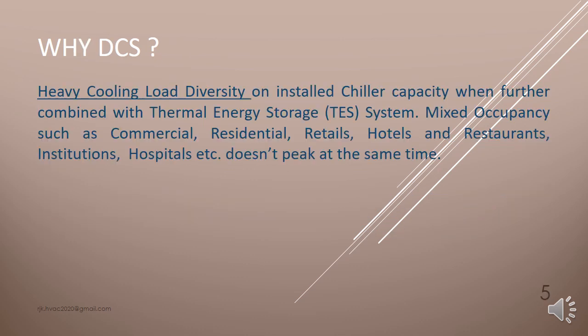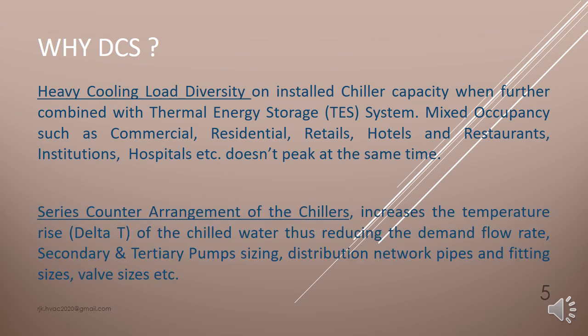Why DCS? Heavy cooling load diversity on installed chiller capacity, when further combined with Thermal Energy Storage (TES) system. Mixed occupancy such as commercial, residential, retail, hotels and restaurants, institution, hospital, etc. doesn't peak at the same time. Series counterflow arrangement of chillers increases the temperature rise delta T of the chill water, thus reducing the demand flow rate, secondary and tertiary pump sizing, distribution network pipes and fitting sizes, valve sizes, etc.